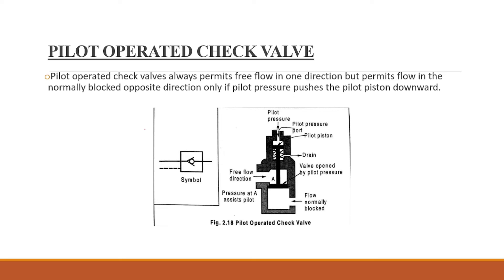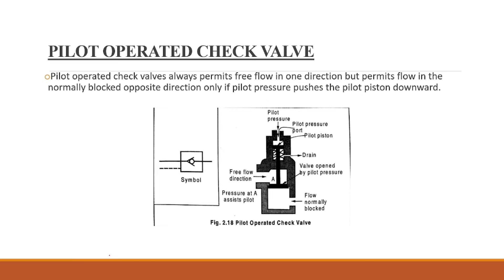The pilot-operated check valve permits flow in one direction, but normally blocks flow in the opposite direction. However, when an external pilot pressure pushes the piston downward, the piston allows flow in the opposite direction as well. The flow is allowed in the free-flow direction normally, and the pilot pressure enables reverse flow.